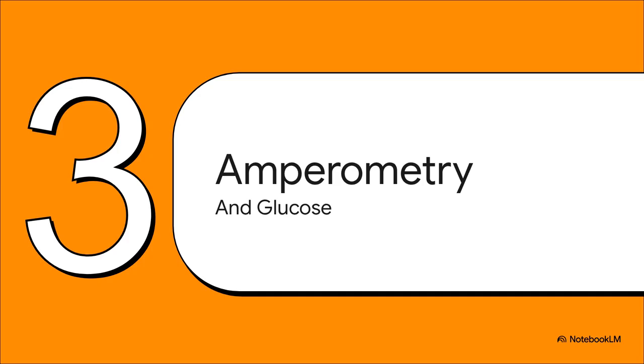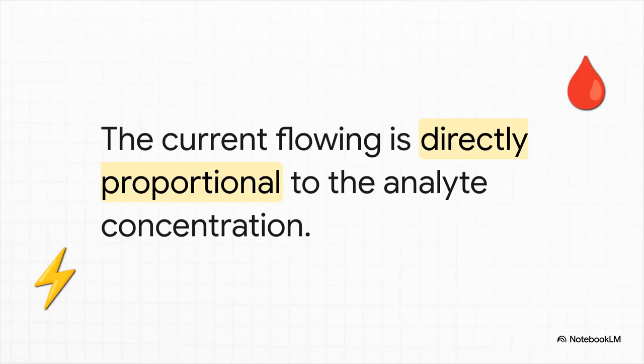Okay, let's see how this all builds into the specific method they did choose for glucose sensing. Amperometry. This essentially became the gold standard for those early biosensors. The crucial takeaway here is that in an amperometric biosensor, the amount of current flowing directly tells us the concentration of our target, which in our case is glucose. The fundamental rule of thumb here is actually quite elegant. Biological redox reactions naturally involve the movement of electrons. Amperometry works by applying a specific potential between 2 electrodes to force that oxidation or reduction reaction to happen. The resulting flow of electrons? Well, that's our current. More target molecules mean more electrons moving, which means higher current. It's a beautifully direct relationship.